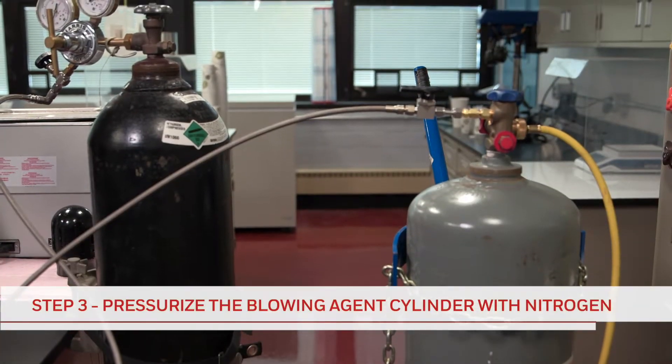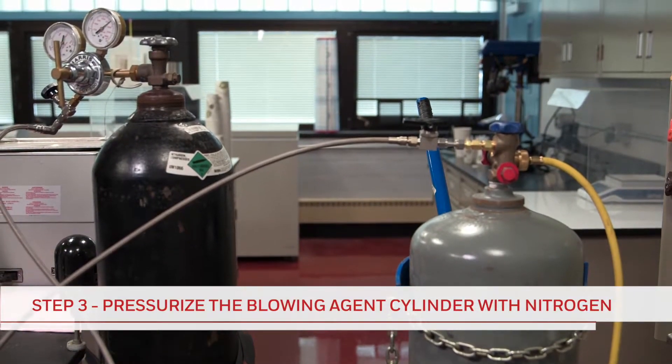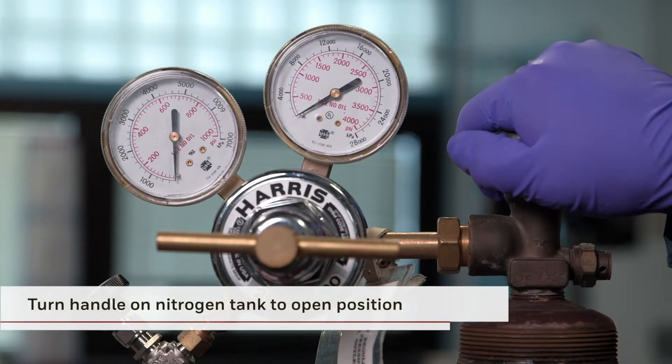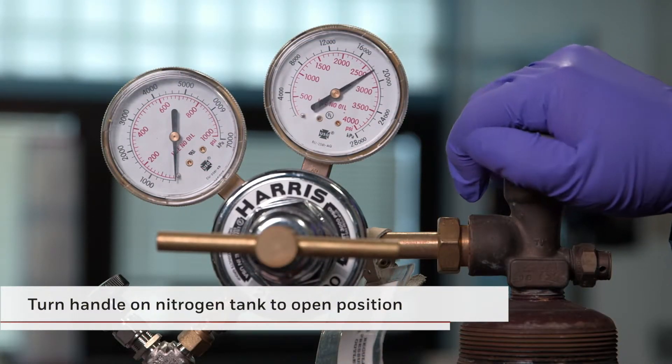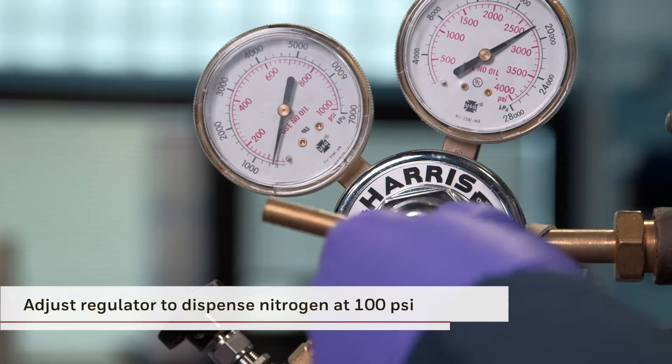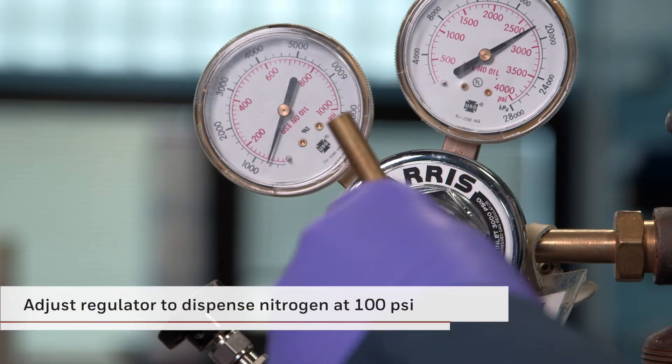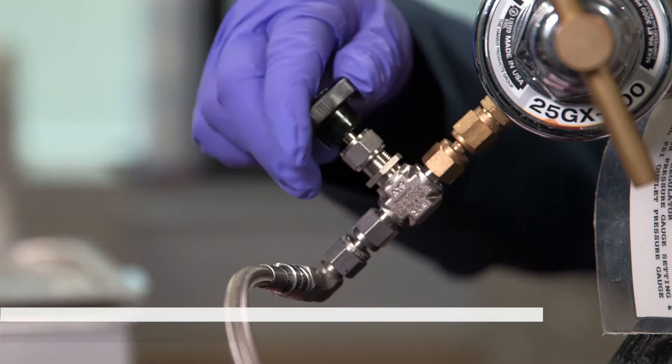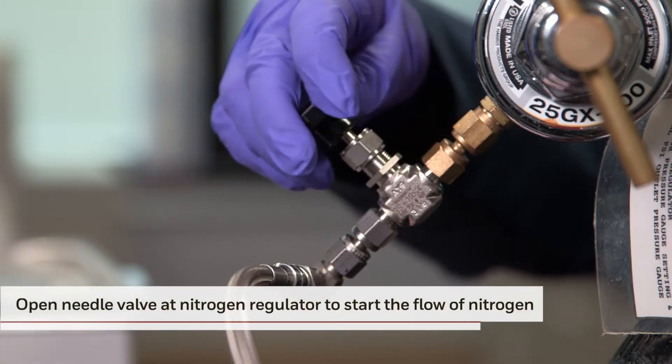Now that the lines are connected, the process of pressurizing the blowing agent cylinder can begin. First, turn the handle on the top of the nitrogen tank to the open position. Adjust the regulator to dispense the nitrogen vapor at 100 psi pressure. Now, open the needle valve at the nitrogen regulator.